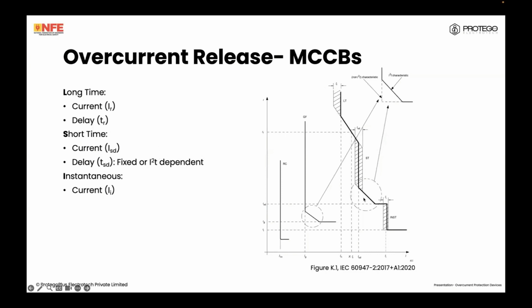So if you look at this part of the curve, we'll just start from the beginning again. IR, you're changing essentially the overload current value. TR, you're changing the time it will wait to trip under overloads. ISD, which is your short time current, you're changing the tripping current for short circuits. And TSD, you're changing the delay. You're assigning a delay essentially to the short time current value here. And it can be either an I squared T characteristic, so depending on the magnitude of the short circuit current within those defined values, it will trip at a certain time, or you can have it fixed. It will just delay a certain amount of time and then go.